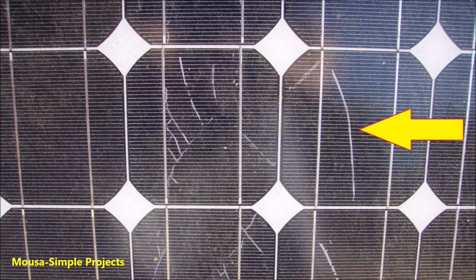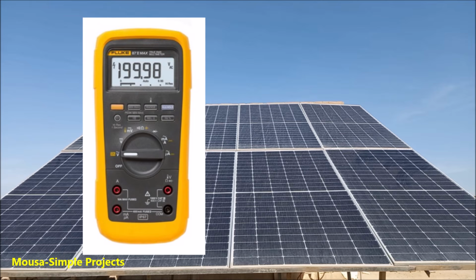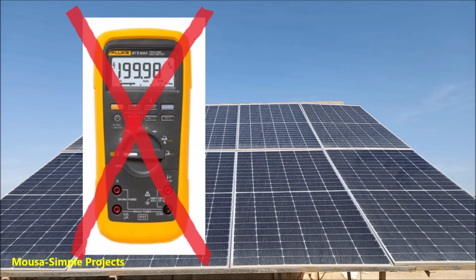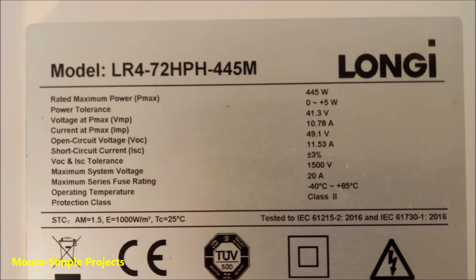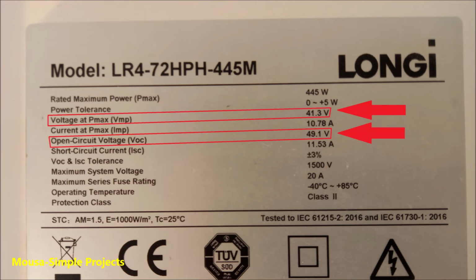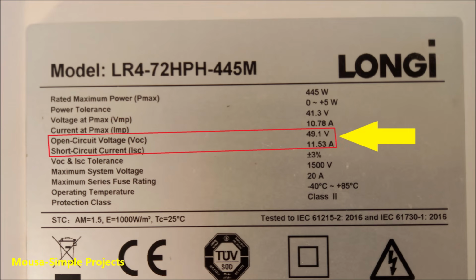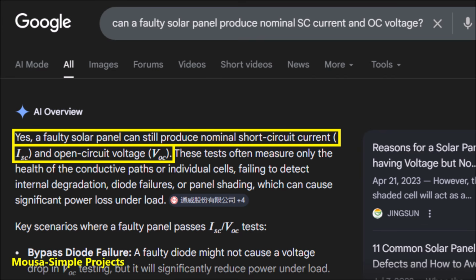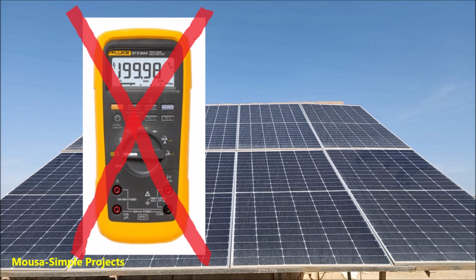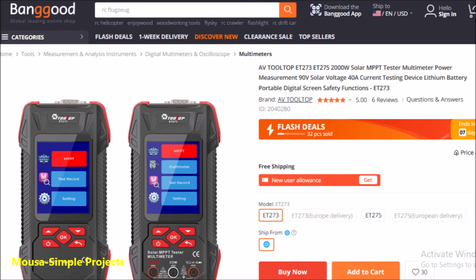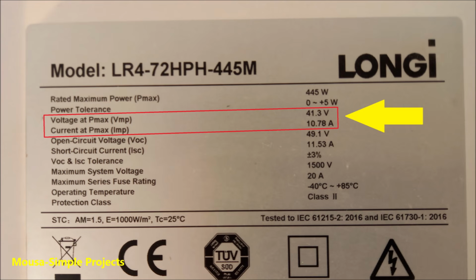So you have to test your solar panels at least once a year. For many years, I used to test them using a multimeter, but it turns out using a multimeter is completely wrong. If you look at the label behind your panel, you can see there are two different voltages and two different currents. The multimeter can only measure the short circuit current and open circuit voltage. According to Google, even a faulty solar panel can still produce the short circuit current and open circuit voltage written on the label, so you can't tell if your solar panel is good or bad just by using a multimeter. You need a solar tester with MPPT to measure the voltage and current at maximum power.